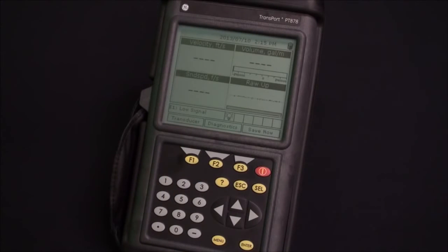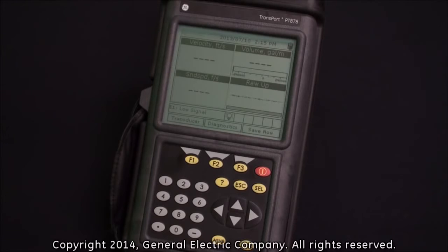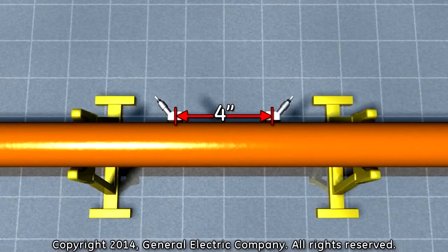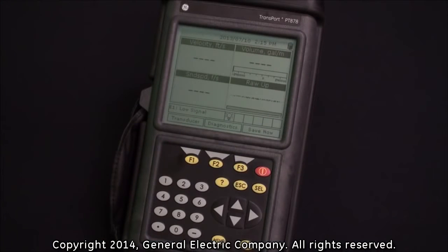After the PT878 flow meter has been programmed, the meter will give you a transducer spacing based on the number of traverses selected. The spacing is the distance between the transducers to be installed. Obtain the spacing and number of traverses from the PT878 before installing the equipment.